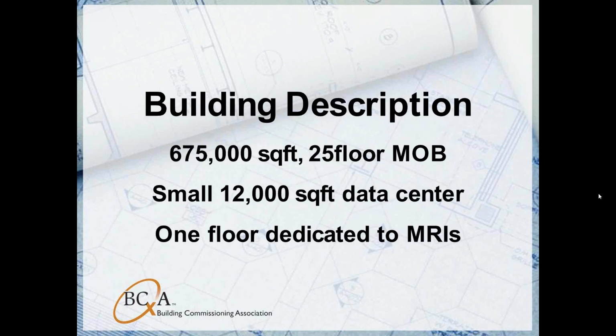So just going into the kind of building we were looking at: a 675,000 square foot, 25-floor medical office building that's part of a larger hospital campus. The building has a small 12,000 square foot data center. The data center is served by some Liebert units that sit in the space, and those units are fed chilled water from the chilled water plant. An entire floor of the building is dedicated to MRIs and CT machines, and those units also utilize chilled water for their process load. Another important fact about the building is that it's an electric-only building, so there's no gas service to the building, meaning all of the heating is done with electric.